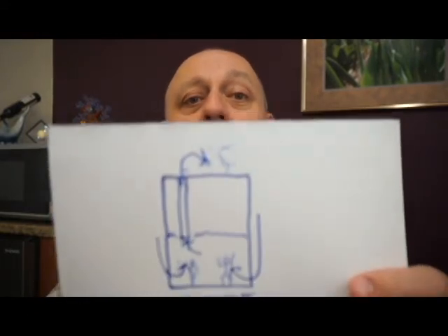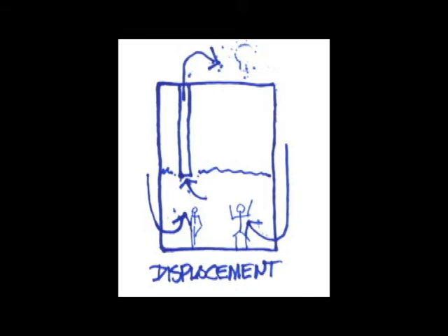And so let me show you another diagram in a taller room. This diagram would be something like a retail warehouse where you have a very tall room, and we're bringing air in here at the bottom, and we're sucking it out at, say, 8 feet above the floor. The reason why that's valuable is because you're not cooling the space above that 8-foot line.